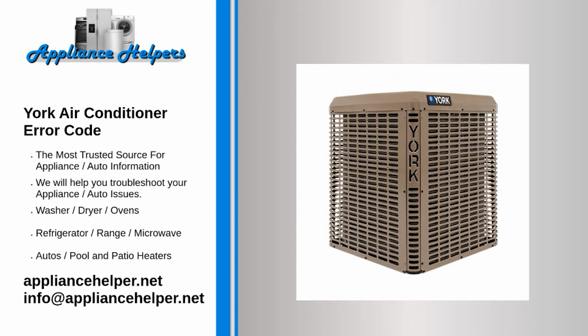Problem: Indoor EEPROM (electrically erasable programmable read-only memory) error. Code E1. Problem: Indoor and outdoor unit communication malfunction. Code E3. Problem: Indoor fan speed malfunction. Code E4. Problem: Indoor room temperature sensor error. Code E5. Problem: Evaporator coil temperature sensor error.